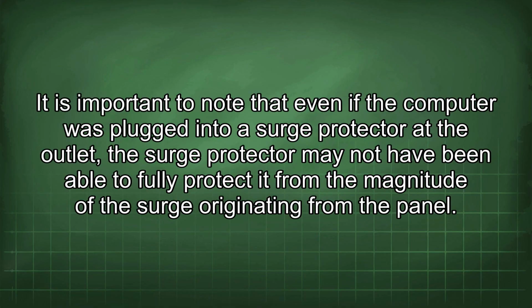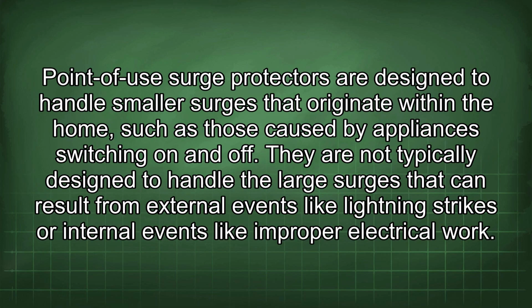It is important to note that even if the computer was plugged into a surge protector at the outlet, the surge protector may not have been able to fully protect it from the magnitude of the surge originating from the panel. Point-of-use surge protectors are designed to handle smaller surges that originate within the home, such as those caused by appliances switching on and off. They are not typically designed to handle the large surges that can result from external events like lightning strikes or internal events like improper electrical work.